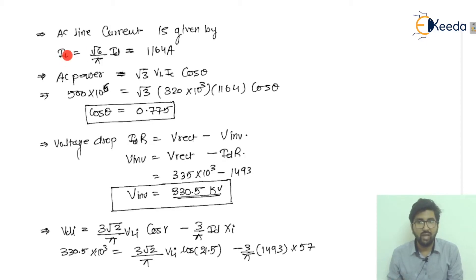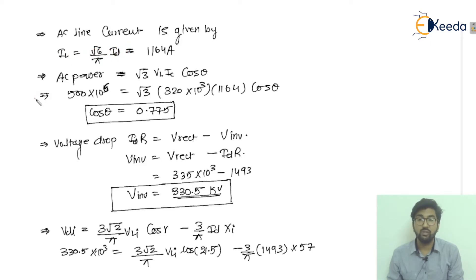AC line current is given by IL = √6/π × ID. Please remember this formula as it will be used in most numericals. So IL = √6/π × 1493 = 1164 amperes.